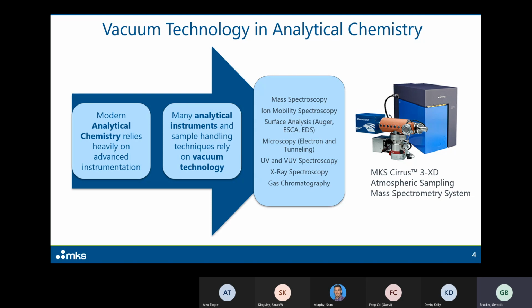Anywhere from mass spectroscopy, where we have to ionize samples and separate the ions based on mass to charge ratio, and vacuum is required for that. Ion mobility spectroscopy, where we have to move ions through a drift tube with very controlled gas flow and pressure conditions and a counter electric field. Surface analysis, more and more, Auger, ESCA analysis: ultra high vacuum conditions are required to make sure that we have very good starting conditions for the substrates.